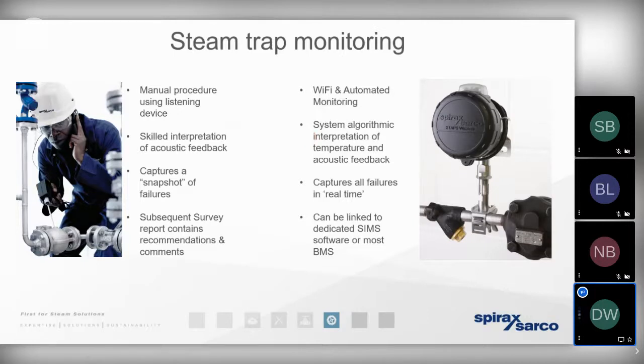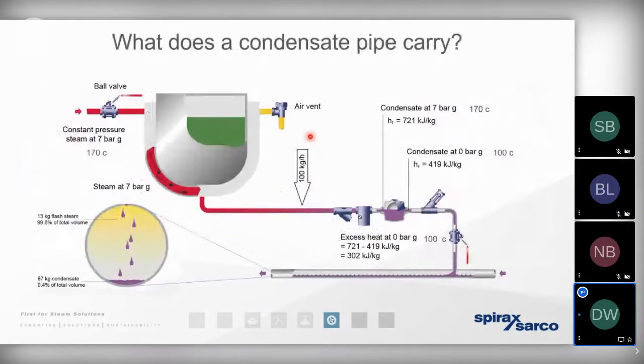So I also want to consider what condensate actually is. So let's take a typical steam using process here. And you can see the jacketed vessel on the screen. It's been designed to condense 100 kilograms per hour of steam at a pressure of 7 bar gauge and at a temperature of 170 degrees C.